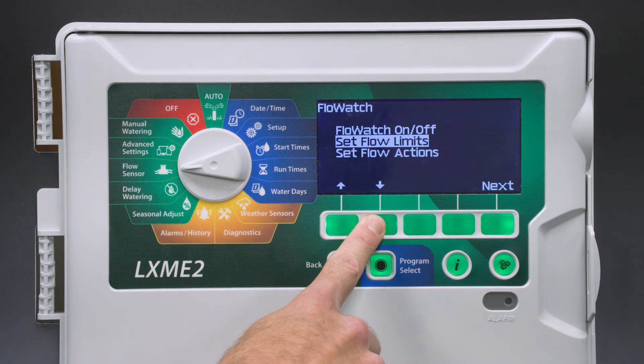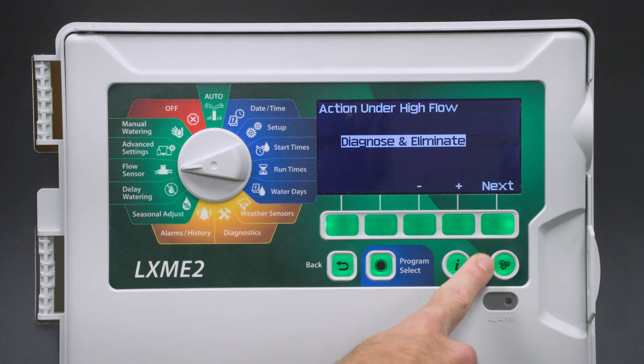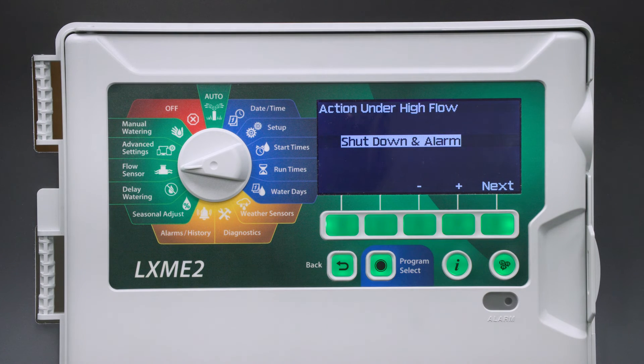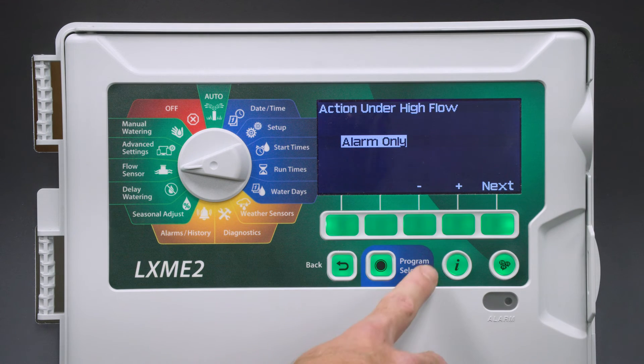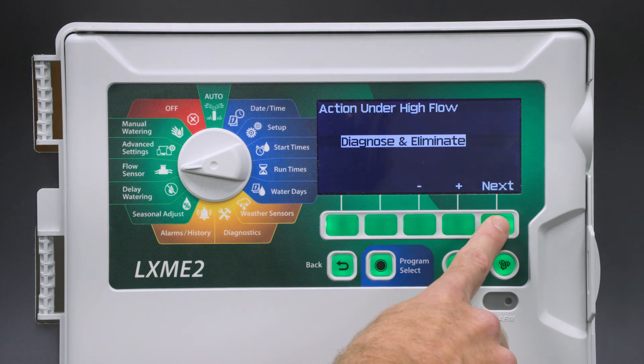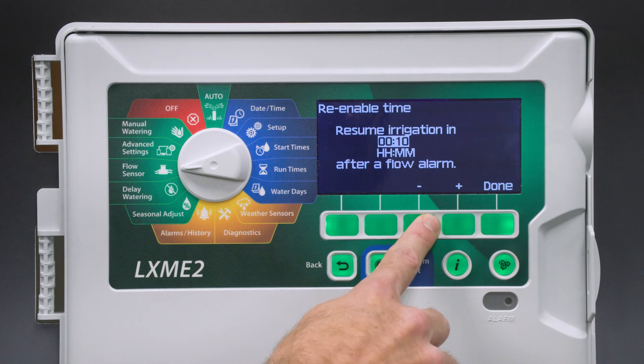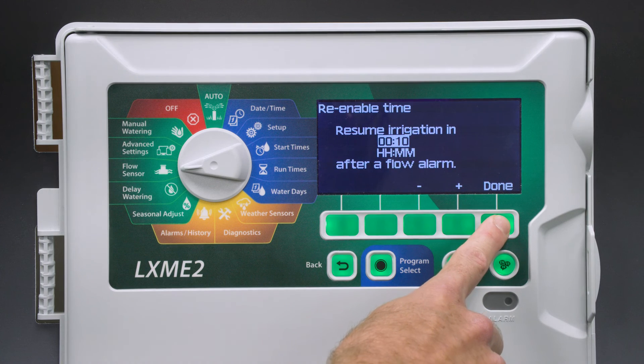Next, we're going to set the flow actions. Diagnose and Eliminate is the default — when it detects a low or high flow on a station, it will first test that station, then turn off that station and continue running the other stations. We can set it to Shut Down and Alarm, which shuts down the whole system and sets an alarm. Or we can set it to Alarm Only, which will run the irrigation as scheduled but show an alarm. We'll set it to Diagnose and Eliminate. We're also going to set the re-enable time, so that once a condition is tripped and all irrigation shuts down, once it's diagnosed, the remaining stations will start up again. We'll set it for 10 minutes and select Done.